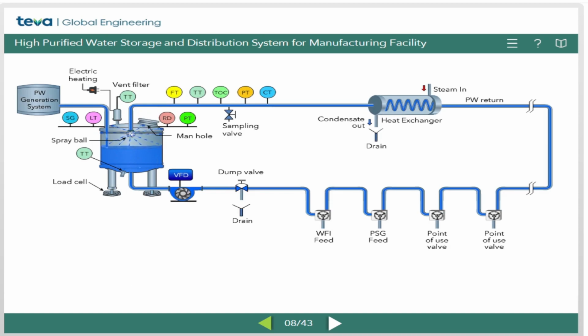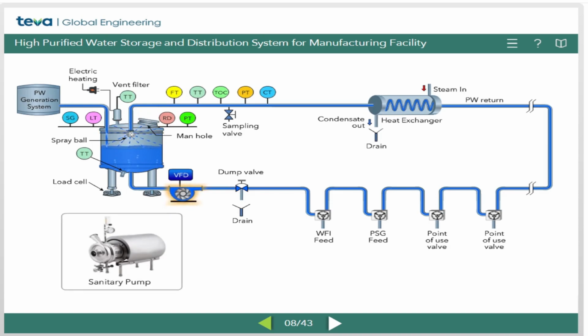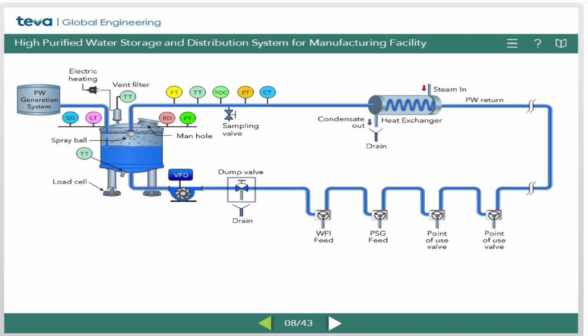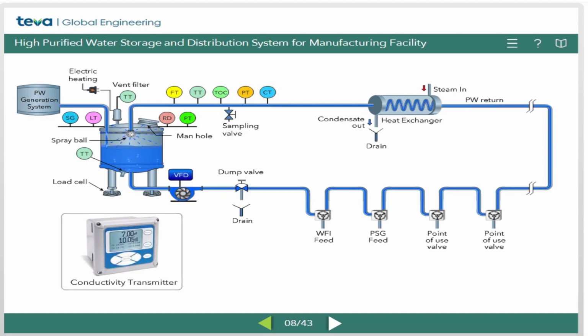PW from the tank is supplied to the production rooms using a sanitary pump. This pump is designed to deliver water at each point of use and maintain the distribution loop in positive pressure of minimum 1 bar at any given time. A variable frequency drive should be used to regulate the impeller speed to optimize on the energy consumption while maintaining the pressure. Dump valve is installed in the distribution loop to immediately stop supply to production and dump the water in a situation of quality failure. The dump valve receives command from the conductivity transmitter.